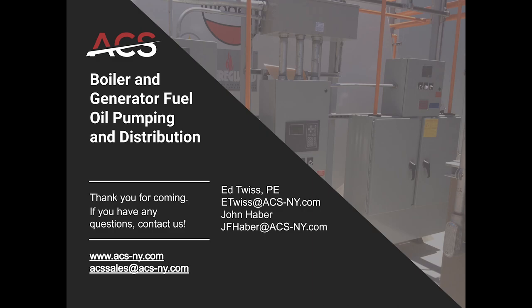Excellent. Next question is, what is the max vacuum a pump can pull? Maximum vacuum is 20 inches. We like to see the pump skids sized and designed at a 15 inch or less vacuum during their normal operation for longevity. You could at times get to 22 to 23 inches of vacuum on your pump, but at that rate, it'll be short-lived.